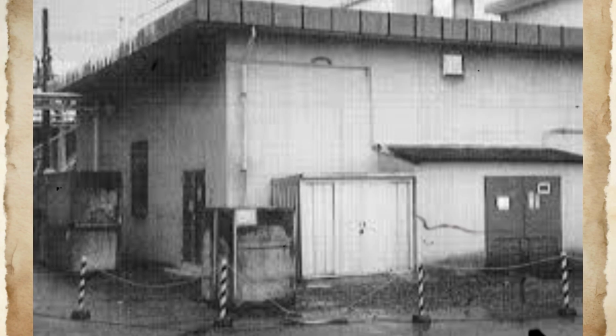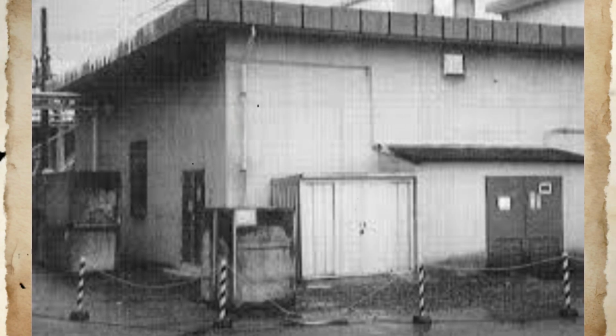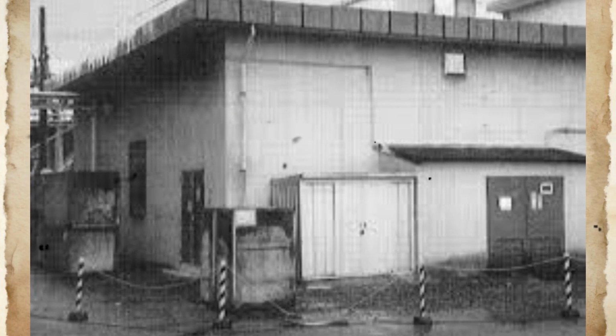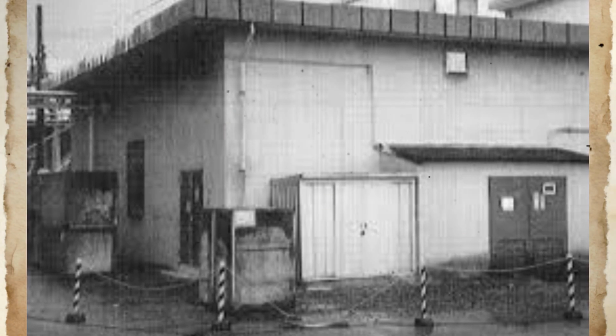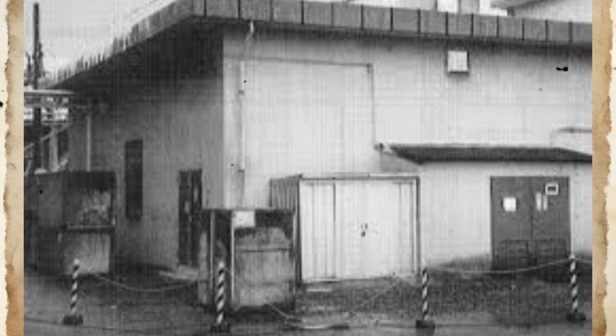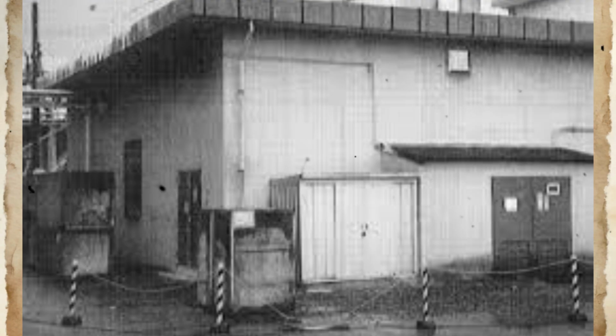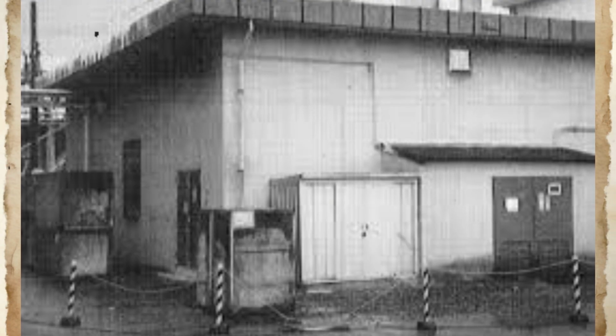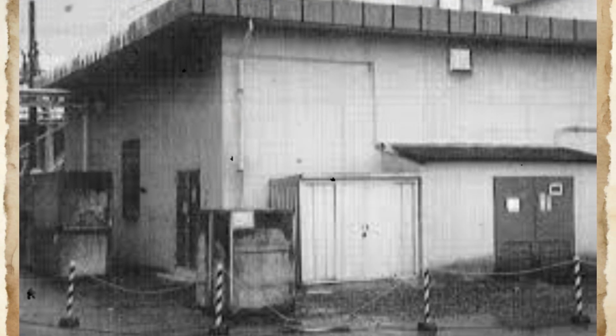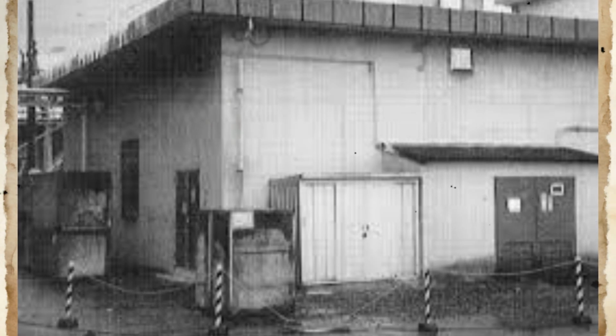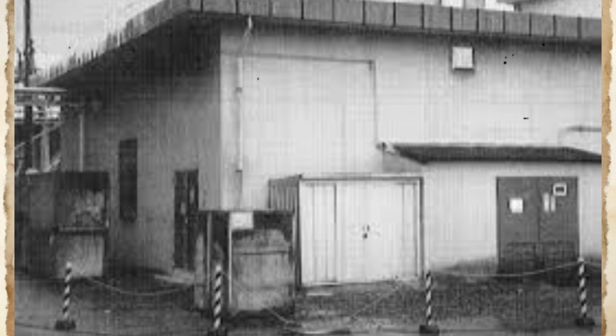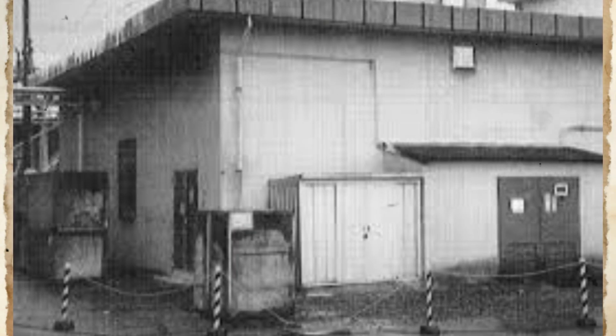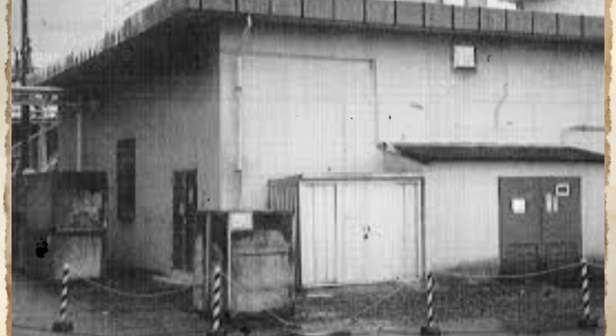The venting operation itself required electrical power to operate isolation valves in the vent line, power that station blackout had eliminated. Manual valve operation became necessary, requiring workers to enter high radiation environments within the reactor building while carrying portable tools and air supplies needed to operate valves designed for remote operation. The complexity of manual operations under emergency conditions meant that venting could not be implemented rapidly, even after the decision to vent had been made.